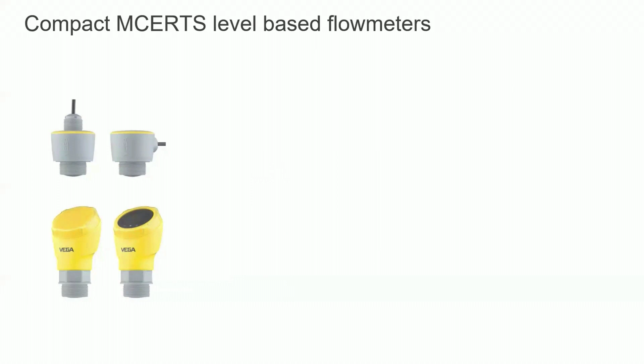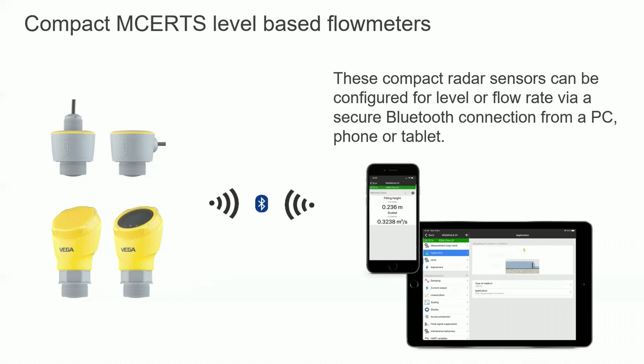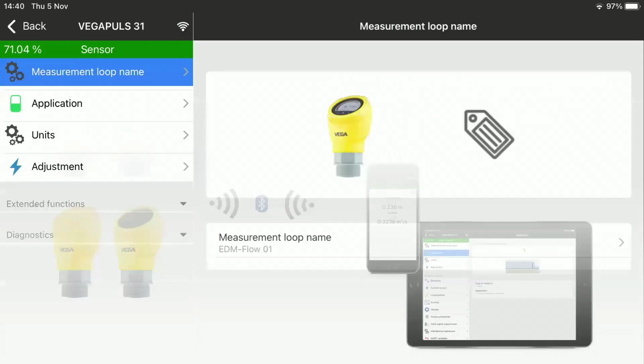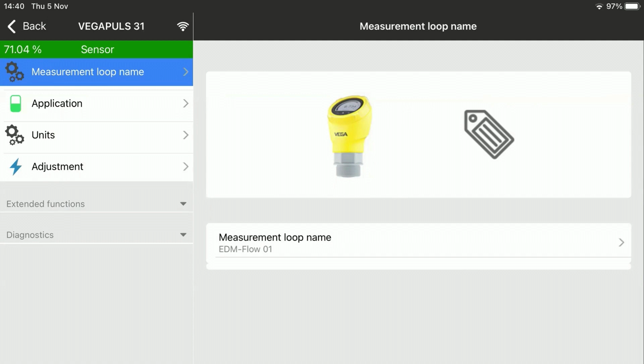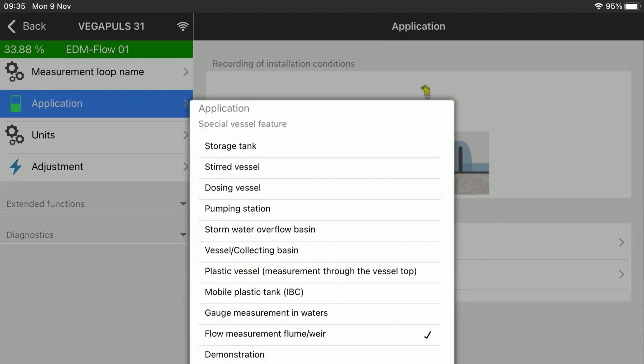So these compact sensors can be configured either for level or for flow using a simple but secure Bluetooth connection from a PC or a phone or via tablet. Let's see what this app looks like. These are screenshots taken from the VEGA Tools app. We're connected to one of the MCERTs certified compact radar level sensors, and we've given it a tag number, EDM flow, to reflect the flexibility of the compact sensor, as we shall see. Okay, the first thing on the application-based setup is to set up the instrument, the radar, to do a particular task. So by selecting an application, in this case, flow measurement in flumes and weirs, the app will automatically configure the instrument to do the correct function.